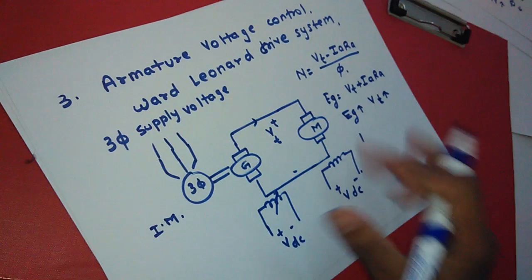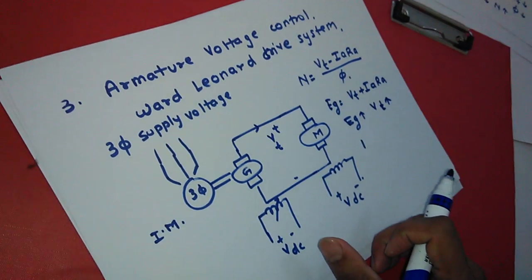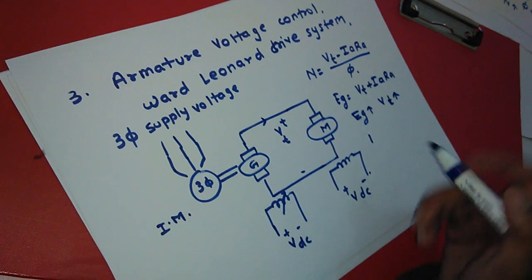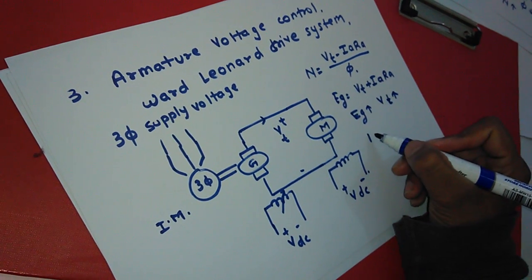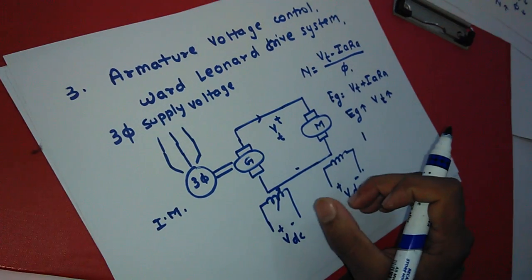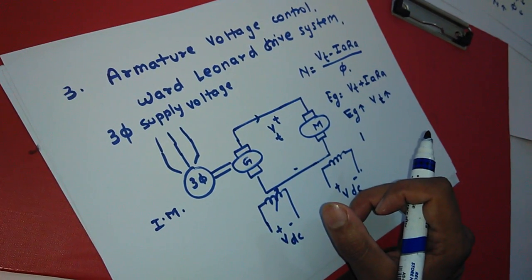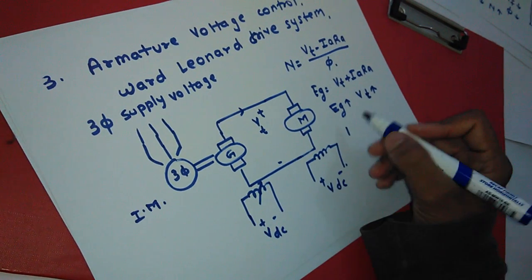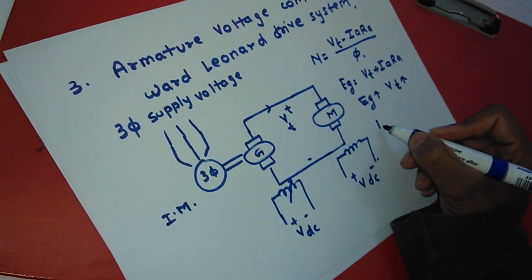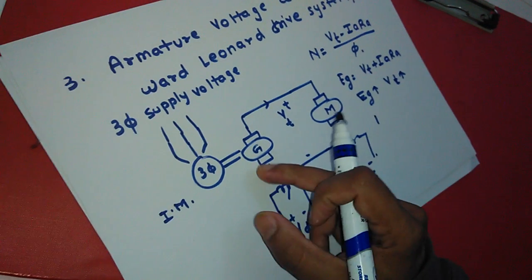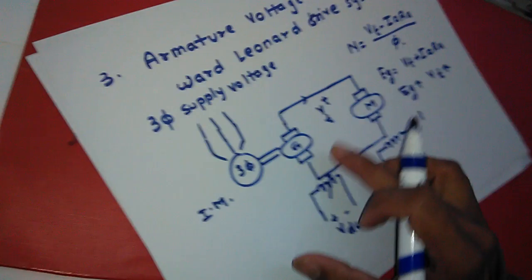This is the speed control by the armature voltage method. The advantage is that we can change the speed over a wide range from zero to base speed. The disadvantage is that it requires a motor-generator set, so it is costly, and it also requires more floor area. This is all about the speed control of DC motor.